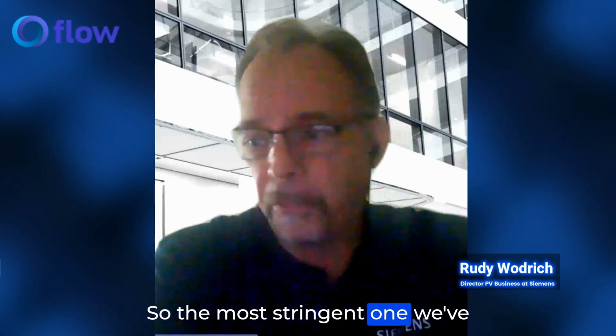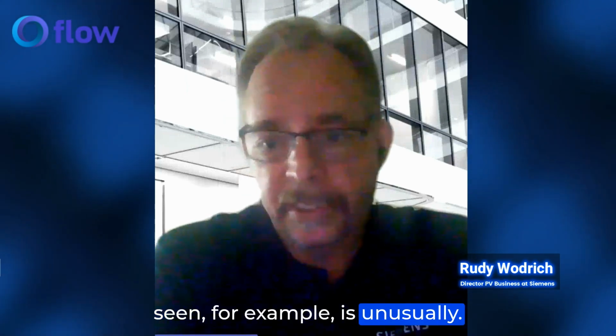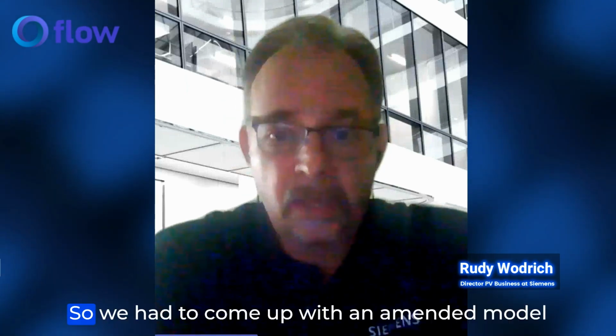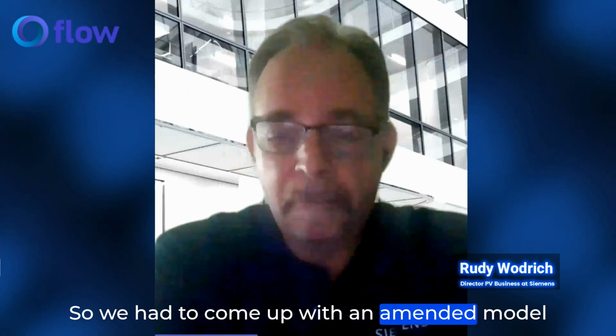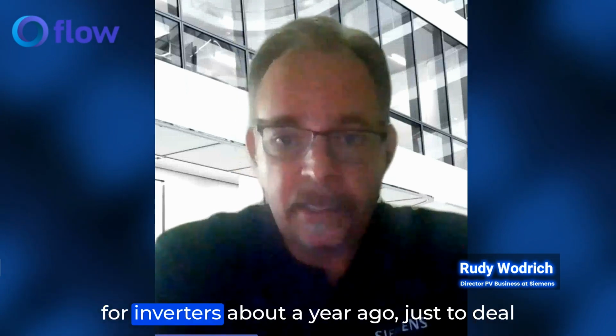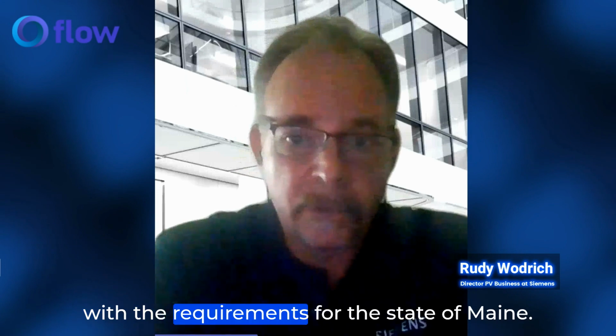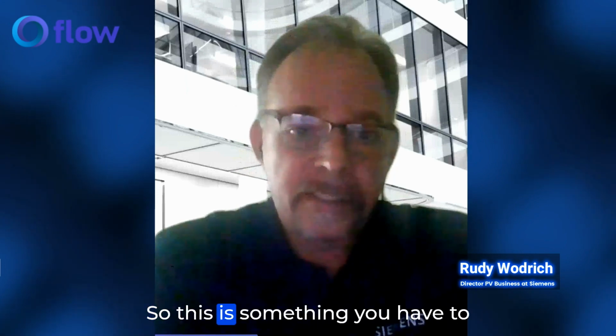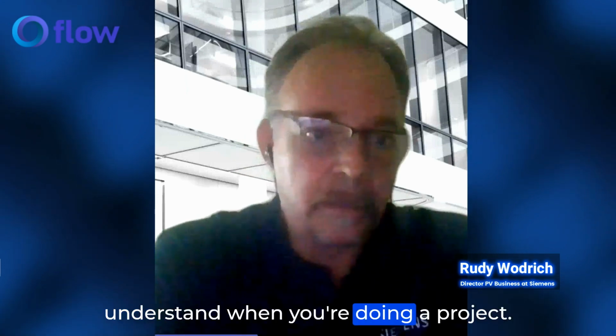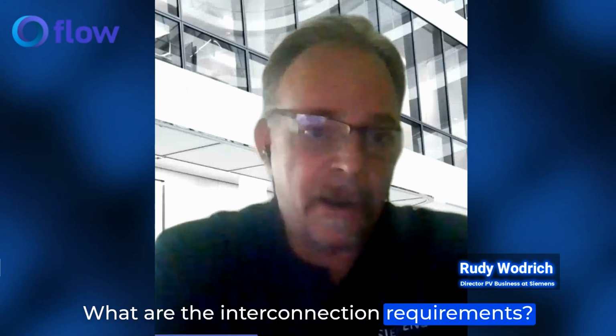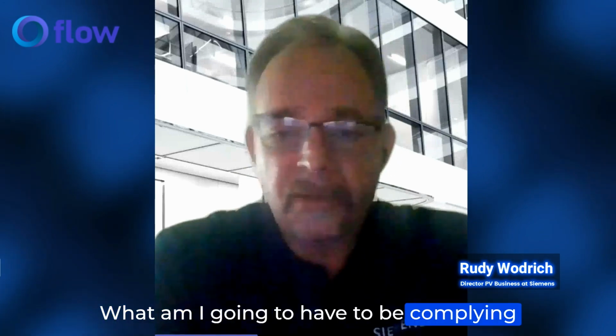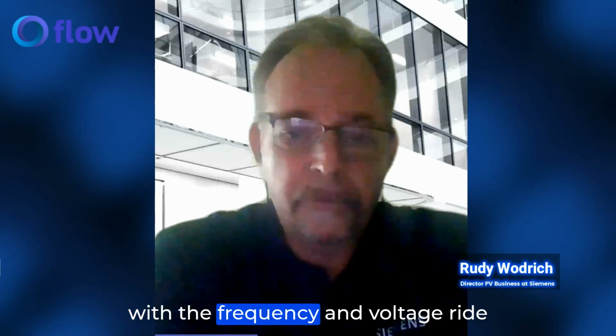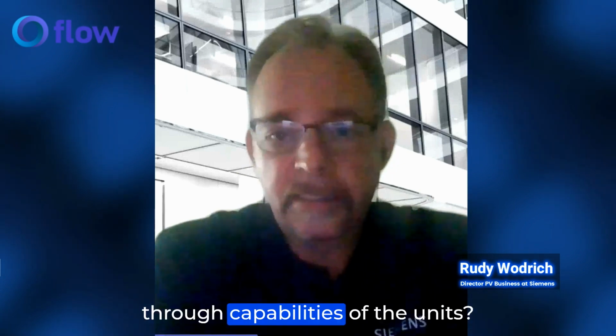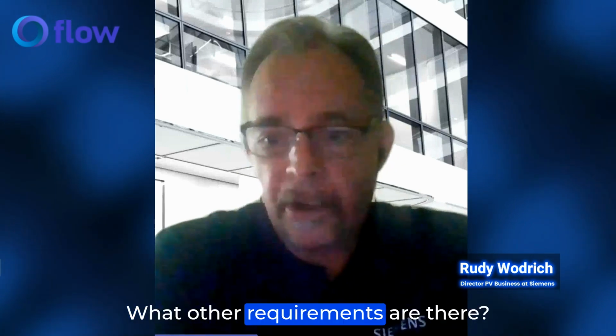The most stringent one we've seen, for example, is unusually in the state of Maine. So we had to come up with an amended model for inverters about a year ago just to deal with the requirements for the state of Maine. So this is something you have to understand when you're doing a project -- what are the interconnection requirements, what am I going to have to be complying with for the frequency and voltage ride-through capabilities of the units, what other requirements are there.